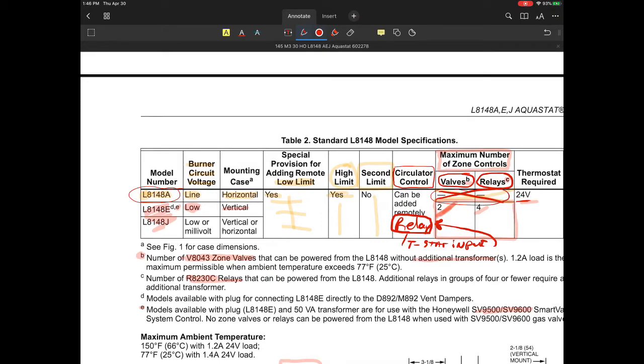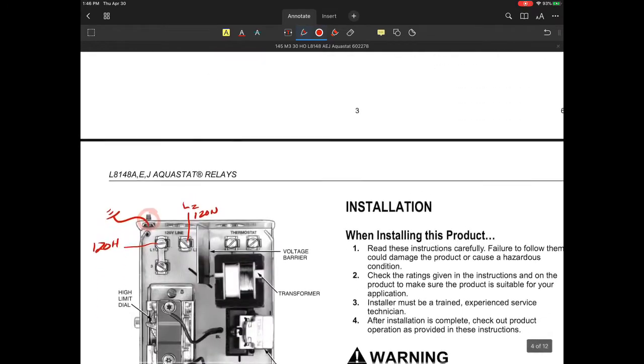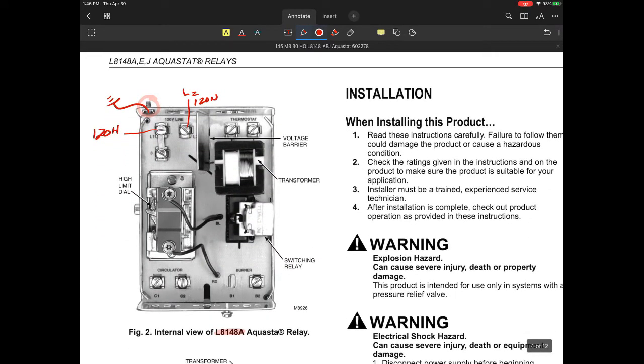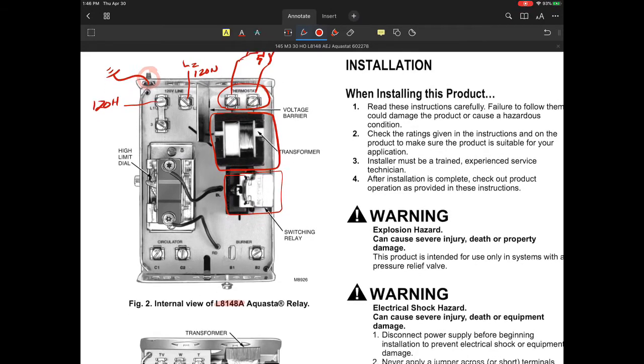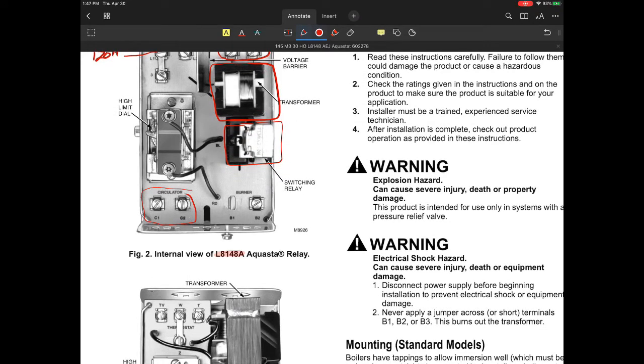Now, on the A model, remember earlier we saw that the A model will not control any zone valves or relays. Now I'm going to show you why that is. This little tiny transformer that's identified here is just enough to literally pull this relay in, and that is all that it can do. The 2 thermostat terminals right here are doing nothing more than completing a circuit. This would go to a thermostat if there's only one zone, or it could go to some relay contact that could complete the circuit. It's either one of those two.